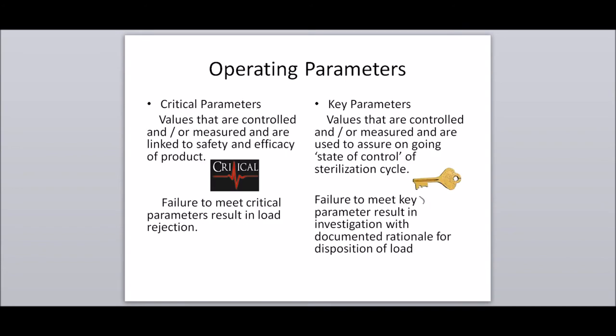There are two types of operating parameters: critical parameters and key parameters. Critical parameters: values that are controlled and/or measured and are linked to the safety and efficacy of a product. Failure to meet critical parameters results in load rejection. Key parameters: values controlled and/or measured to assure ongoing state of control of the sterilization cycle. Failure to meet key parameters results in an investigation with documented rationale for disposition of the load.